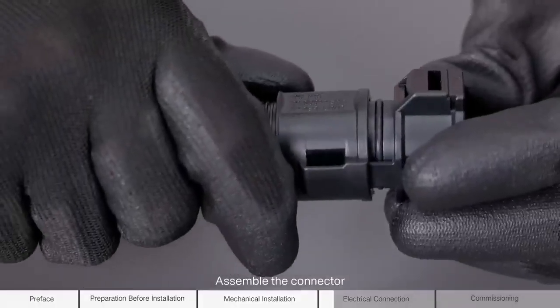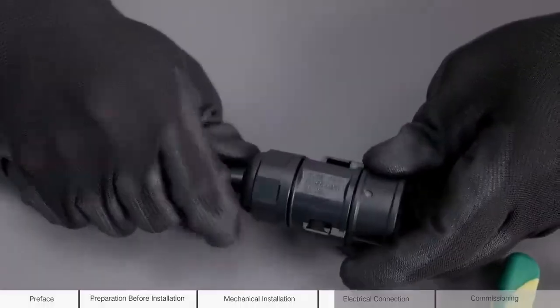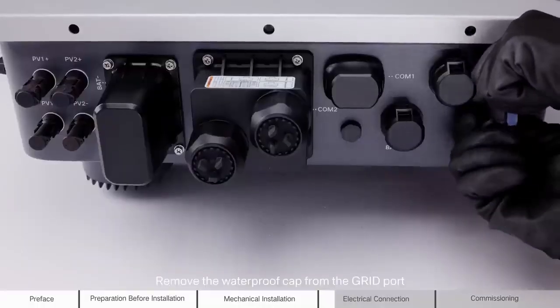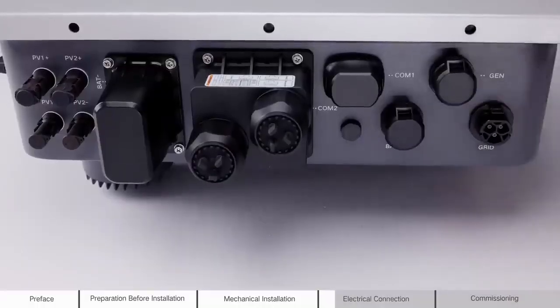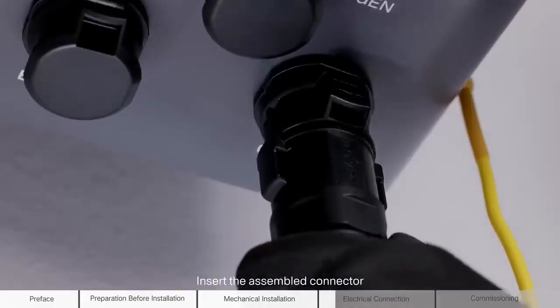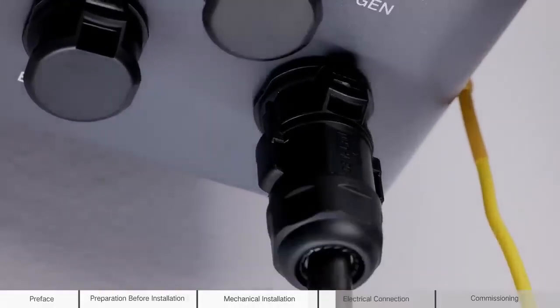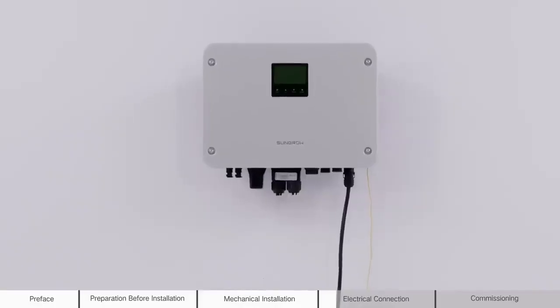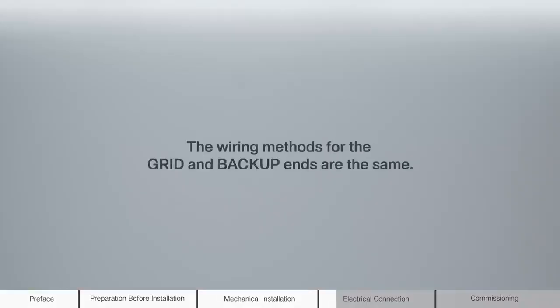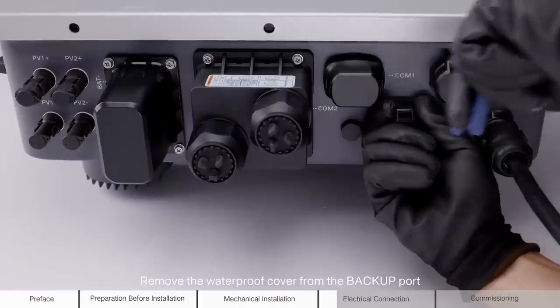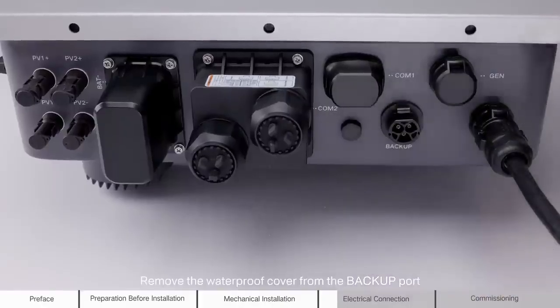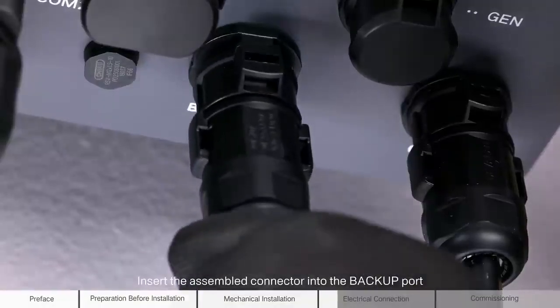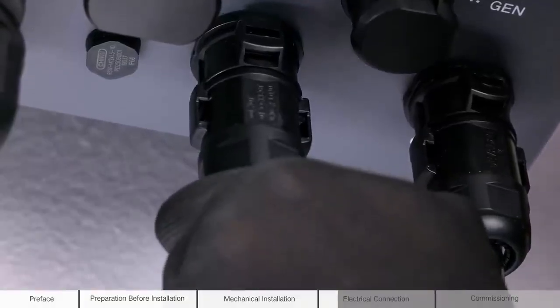Assemble the connector. Remove the waterproof cap from the grid port. Insert the assembled connector into the grid port. The wiring methods for the grid and backup ends are the same. Remove the waterproof cover from the backup port. Insert the assembled connector into the backup port.